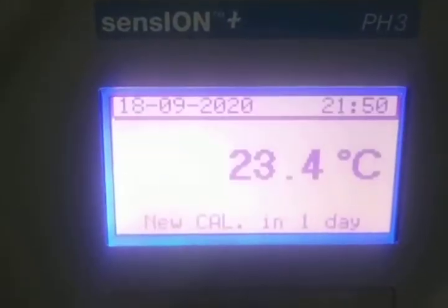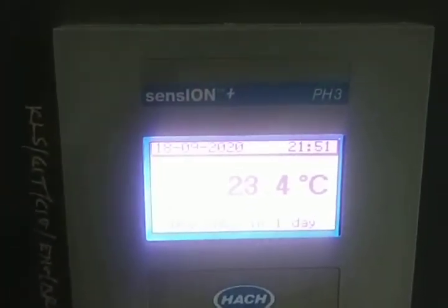So the instrument is calibrated for all 3 buffer solutions. Now we are going to check one water sample. So now we are going to collect the water sample which needs to be analyzed. Before checking the pH of the given water sample, we need to rinse the electrode with deionized water or double distilled water. In this case we are making use of double distilled water, which has been passed through the desalination unit. Now we are going to read the value of the given water sample. Make sure this electrode is immersed properly.